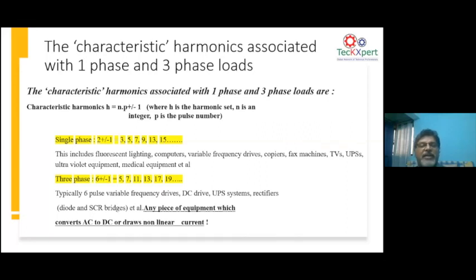When it's characteristic, as I said before, any of these three-phase or single-phase electronic loads are fundamentally doing full wave rectification. Now, if you look at a 6-pulse variable frequency drive, which is conventionally used in a factory, 6 pulse means it has 6 diodes in the circuit. When you have 6 diodes, in the three-phase situation it is 6 plus minus 1. That is how the characteristic harmonic order numbers are generated.